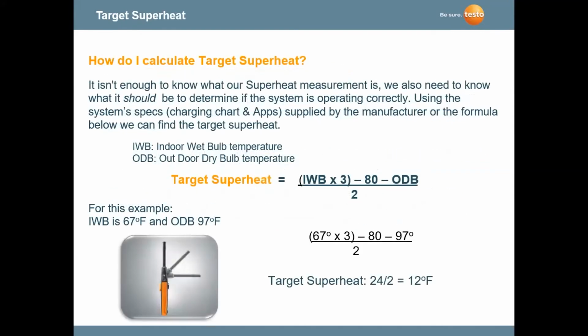Sometimes if we don't have the TXV and we've got a piston type, we have to figure out our targeted superheat. When we figure out our targeted superheat, we have to know the indoor wet bulb temperature and the outdoor dry bulb temperature. In the past, we used to use formulas. We used to use charging charts.